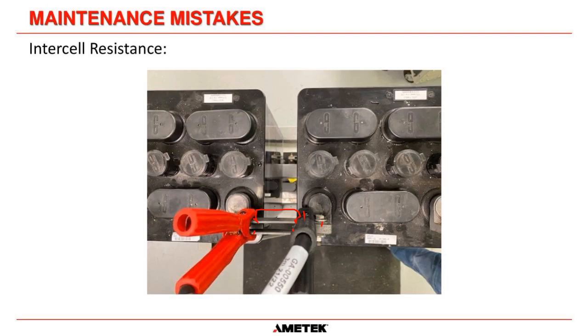You're not measuring the connection resistance there. All you're measuring is that little piece of copper bus bar, and that's a useless measurement, an absolutely useless measurement. That's not going to tell you anything, because that copper bus bar is not going to degrade in any way, shape, or form. What will degrade, actually, let me go back...